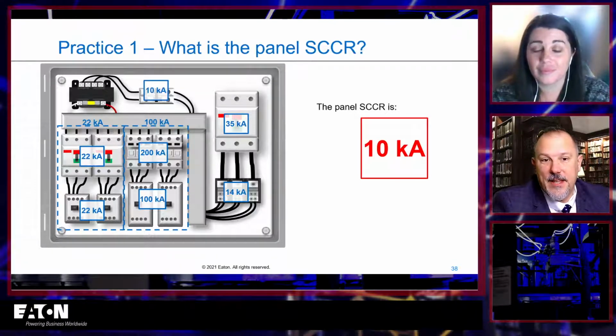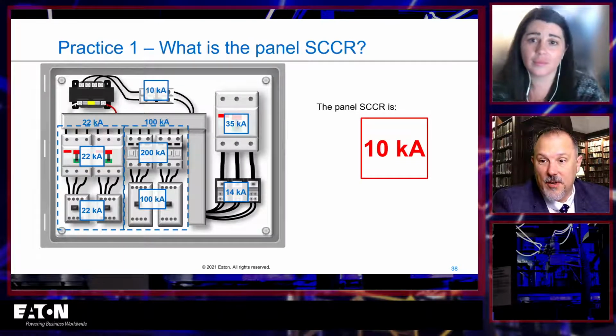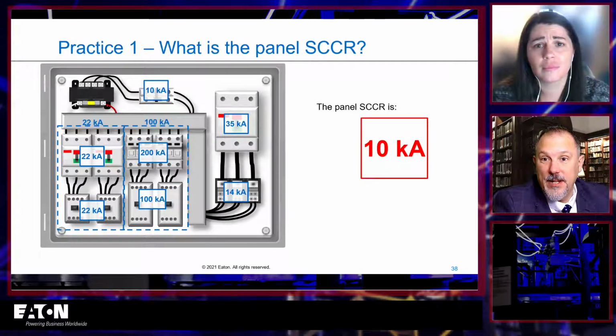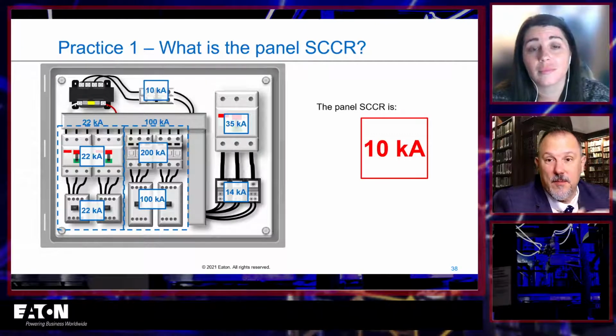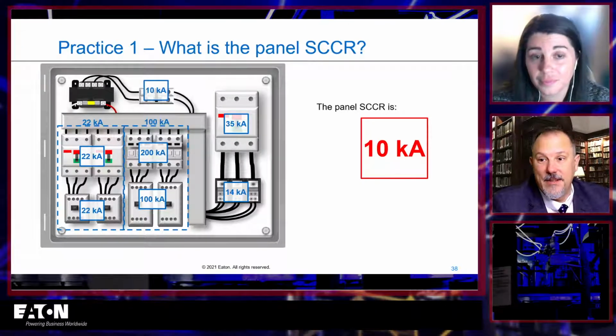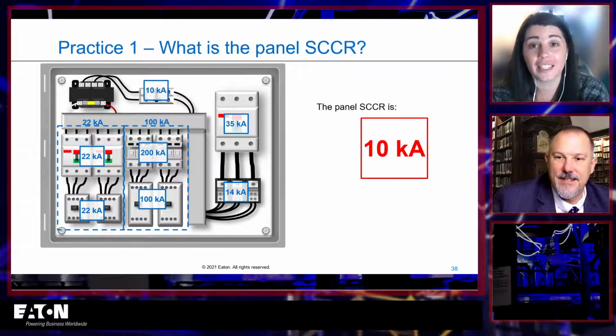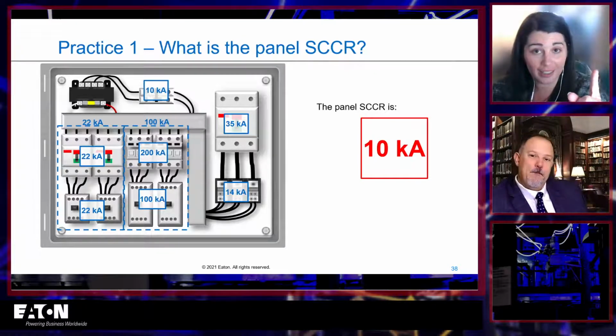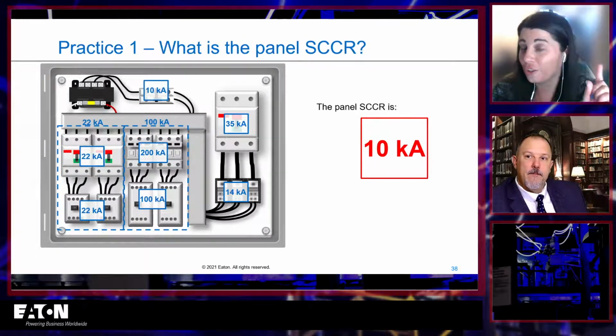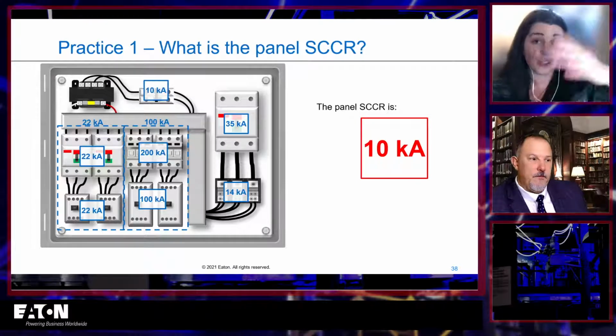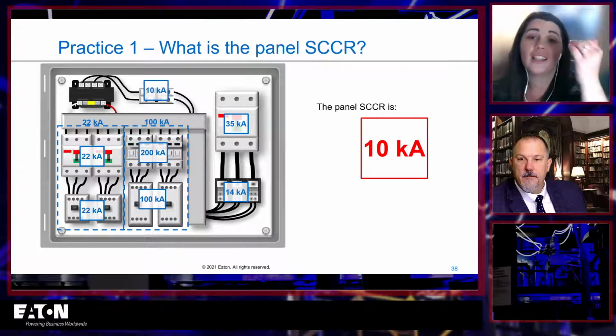It might be that I have to either get a new power distribution block that's rated with that breaker, or I might have to put a fuse upstream of it. And then I can say, okay, now I've increased that one. Yep. So it's a matter of you fix your weakest link, and then you go to the next weakest, until your weakest link is high enough that it's okay.